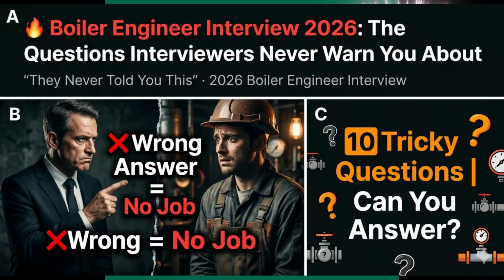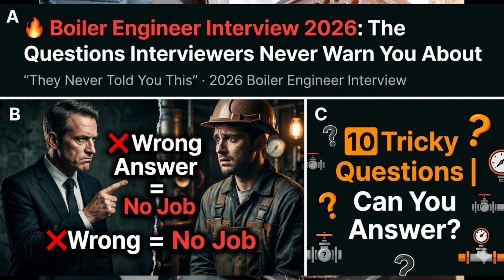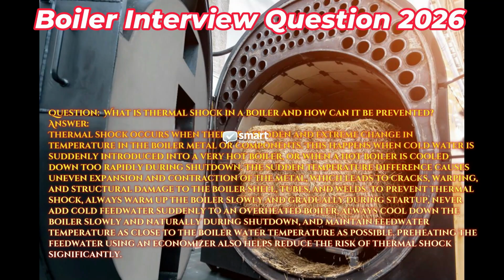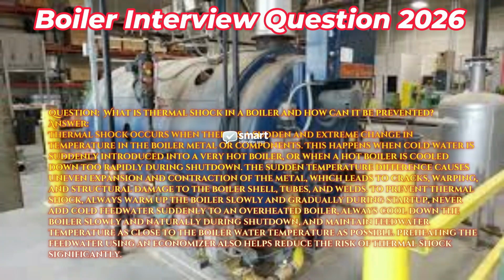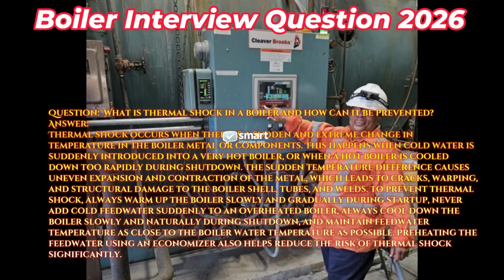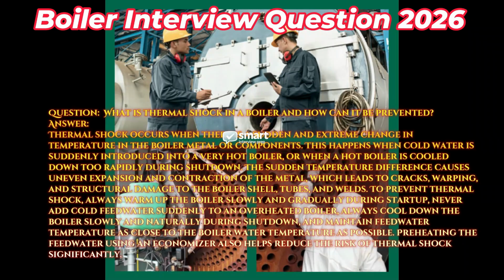To prevent thermal shock, always warm up the boiler slowly and gradually during startup. Never add cold feed water suddenly to an overheated boiler. Always cool down the boiler slowly and naturally during shutdown, and maintain feed water temperature as close to the boiler water temperature as possible. Preheating the feed water using an economizer also helps reduce the risk of thermal shock significantly.